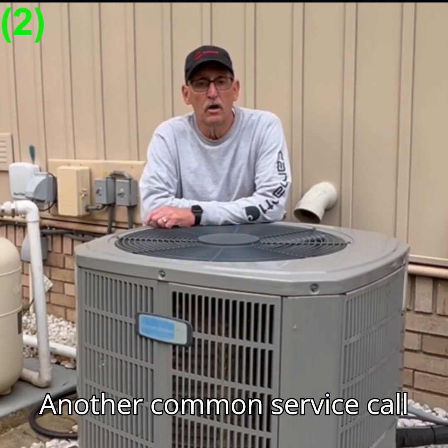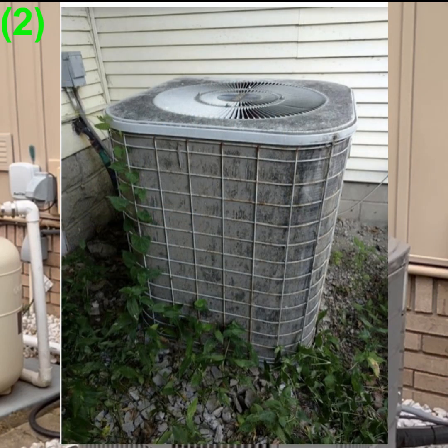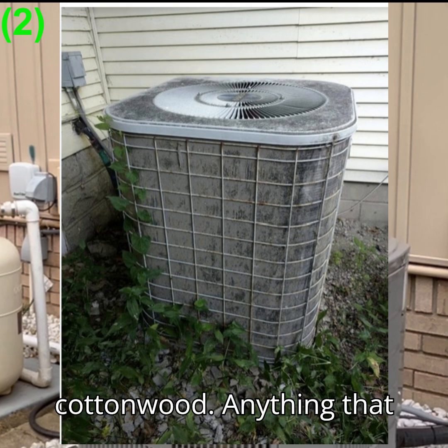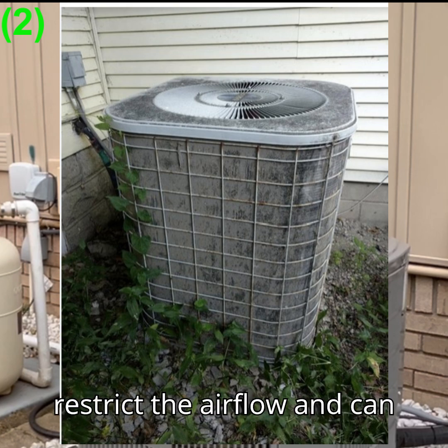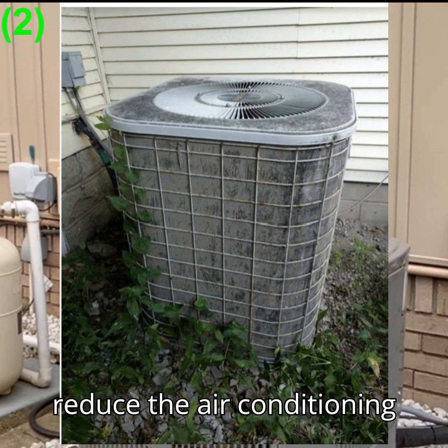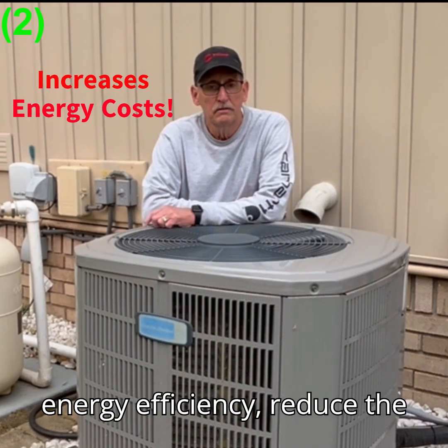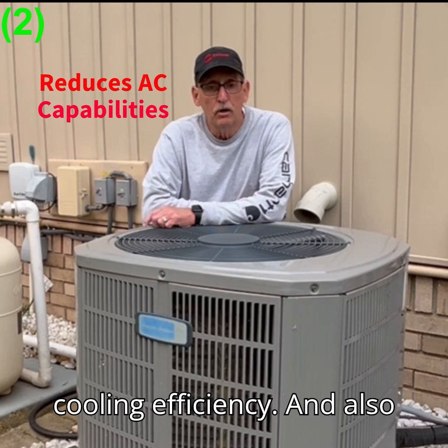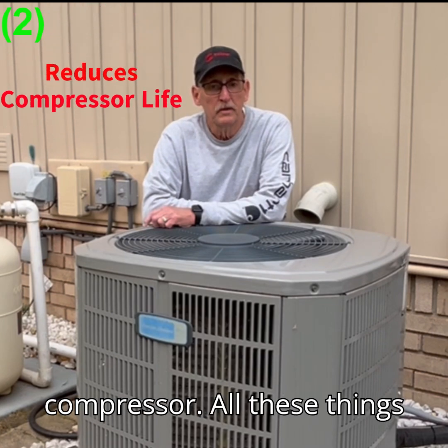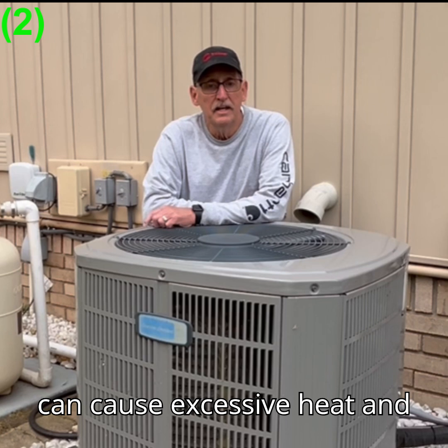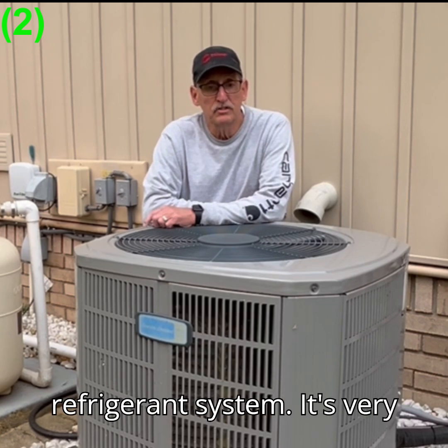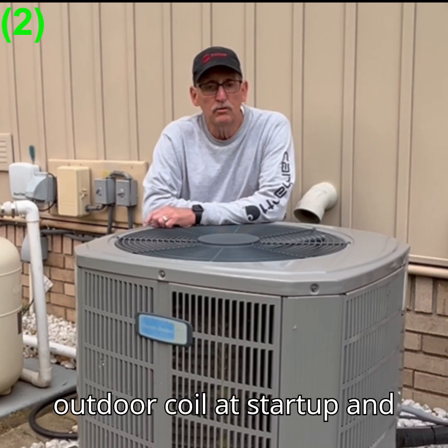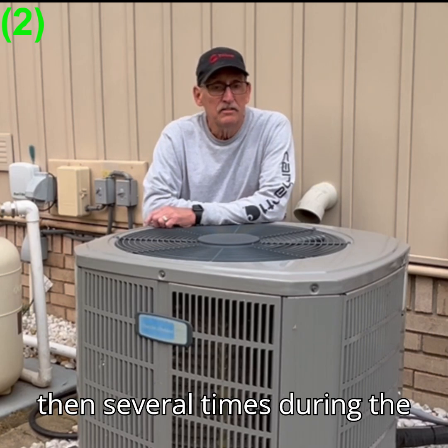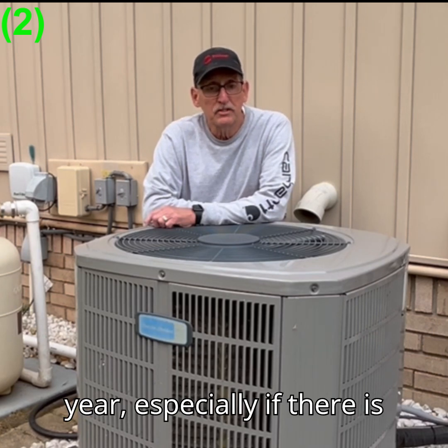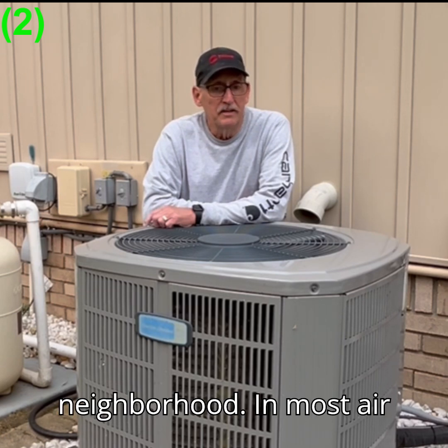Another common service call is a dirty condenser coil, usually caused by a buildup of dirt and debris, cottonwood, anything that circulates in the air. It can restrict the airflow and reduce the air conditioning energy efficiency, reduce the cooling efficiency, and also reduce the life of the compressor. All these things can cause excessive heat and high pressure in the refrigerant system. It's very important to check the outdoor coil at startup and then several times during the year, especially if there is a cottonwood tree in the neighborhood.